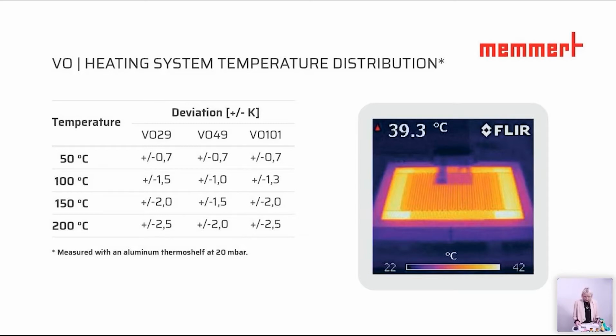When we look at this thermal image, you'll see in the interior a light color, orange getting to red, which means we have very good heat distribution. And if you see the rim of the shelf getting lilac, that means it's getting colder there - because that's where we have contact with the chamber, and the heat escapes to the environment.